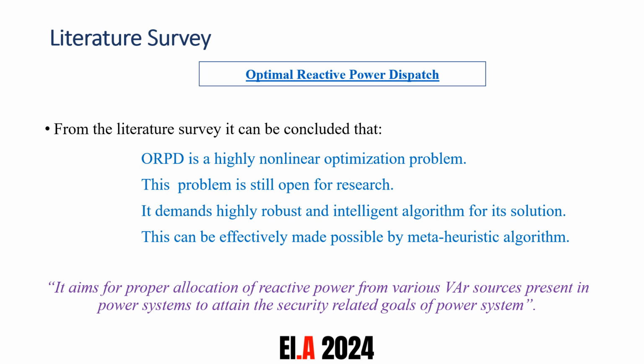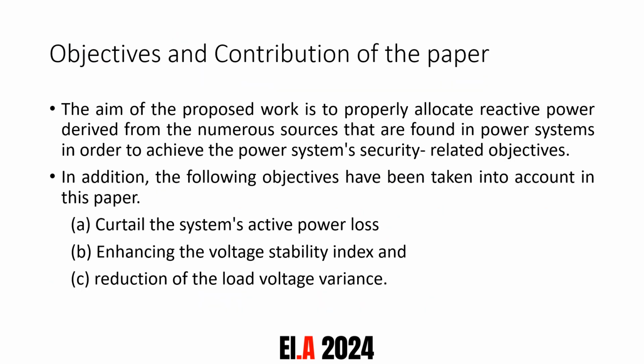From the literature survey on optimal reactive power dispatch, it can be concluded that optimal reactive power dispatch is a highly nonlinear optimization problem, and this problem is still open for research. It demands a highly robust and intelligent algorithm for its solution, and this can be effectively made possible by metaheuristic algorithms. Optimal reactive power dispatch aims for proper allocation of reactive power from various var sources present in power systems to attain the security related goals of the power system. In this paper, we have minimized the active power losses in the IEEE 30 bus system. Also, we have enhanced the voltage stability index and minimized the total voltage deviation.